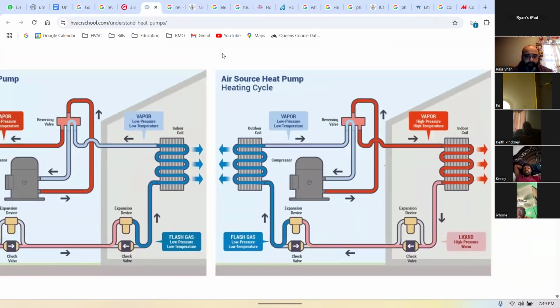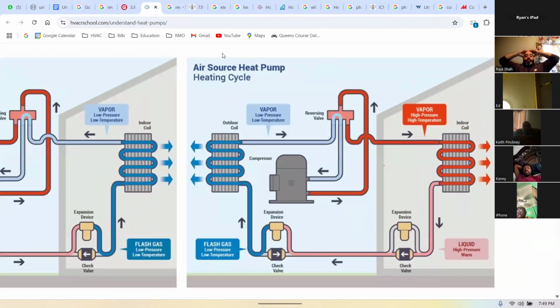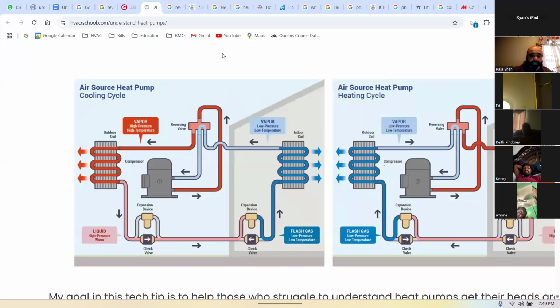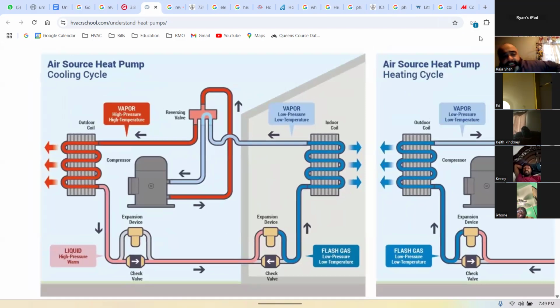Okay, you guys see this? Yes, sir. Now, this is your heating, heat pump, right? Let's go into cooling, actually, to make it easier because you guys are more familiar with the cooling side. So this is a heat pump with the reversing valve. Now, there's something called a water source heat pump, WSHP, very common in the field. What that means is your evaporator coil is still going to be air cooled, still dealing with air, but your compressor, your condenser coil is going to be water.